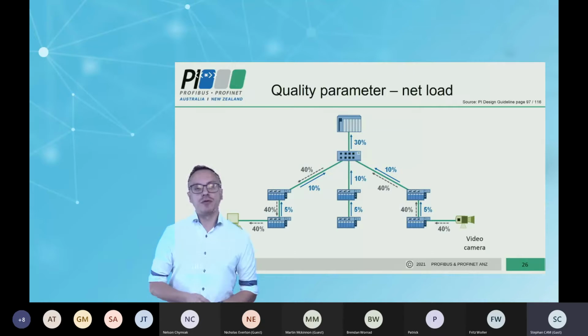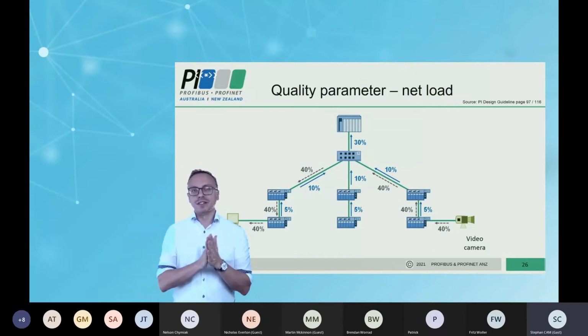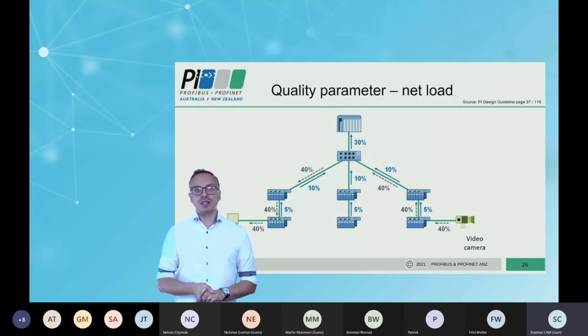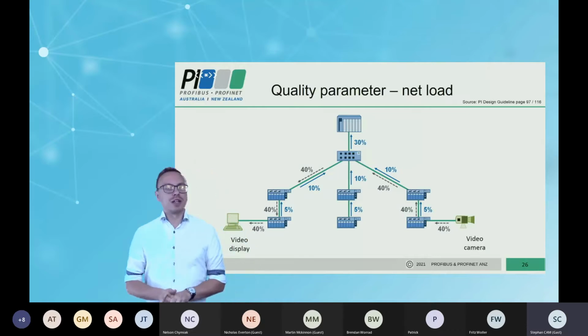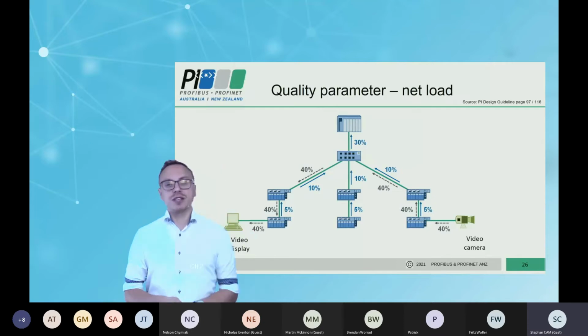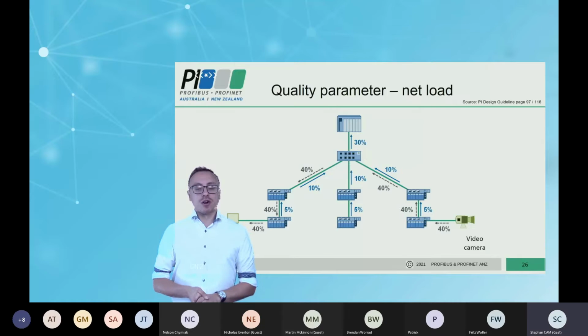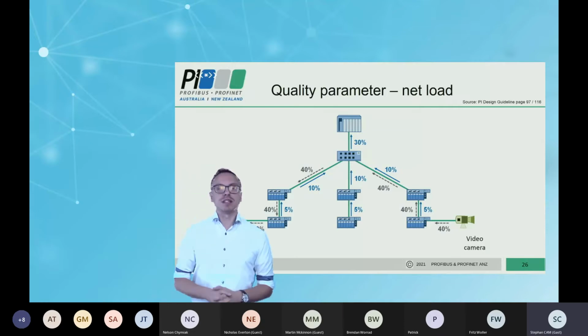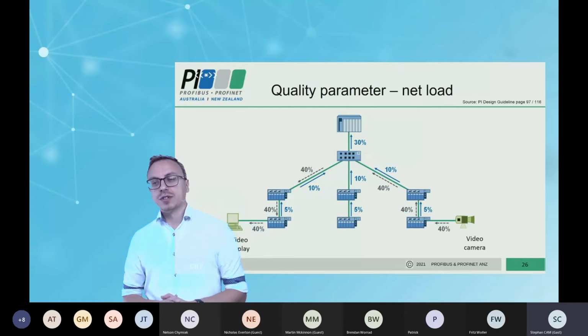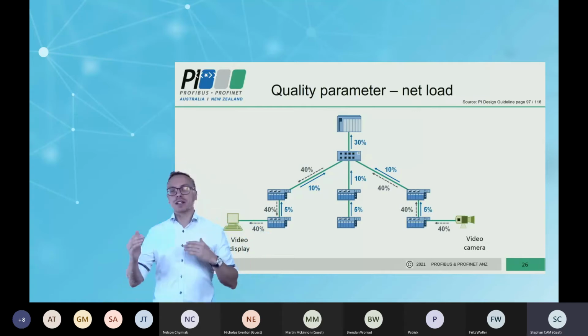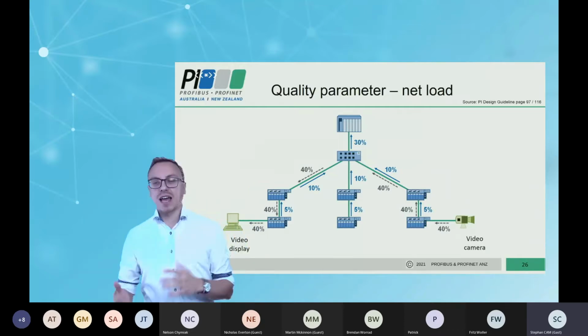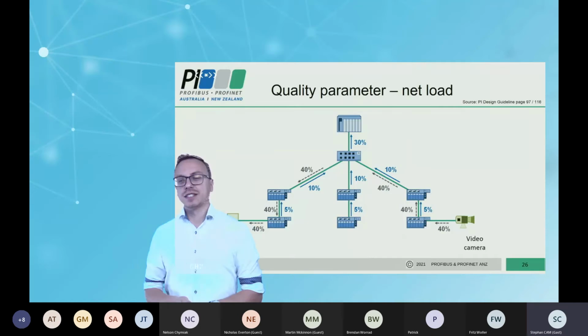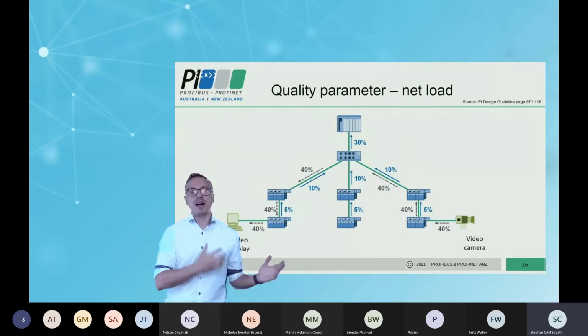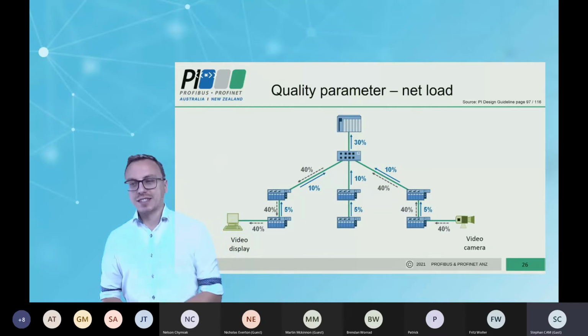Now, if you follow the PI design guideline, you will read that the maximum recommended net load in your system is 20%. If you are over 20%, you have to do something, or you have to look at the reason for such a high net load. And now be careful. For example, if you read the data sheets of a Phoenix PLC, it can only handle 10% net load. So this is why you have to look at how high your net load is in your system and whether the devices can handle this. The good thing is, if your devices cannot handle the net load, you get frame gaps or a high jitter value. But you can find this out very easily with a measurement tool.